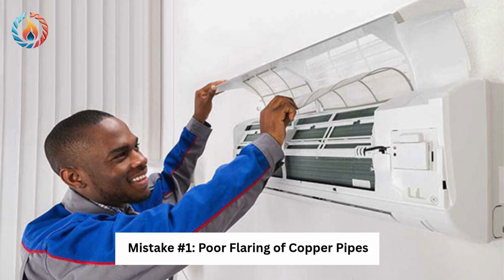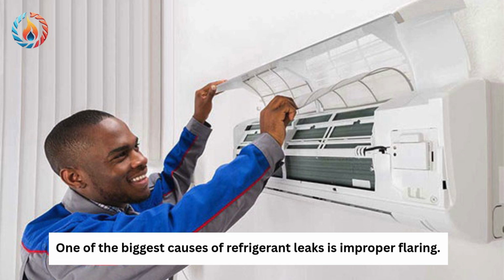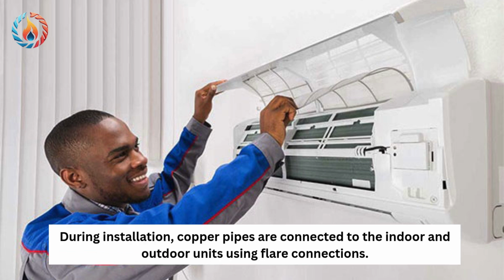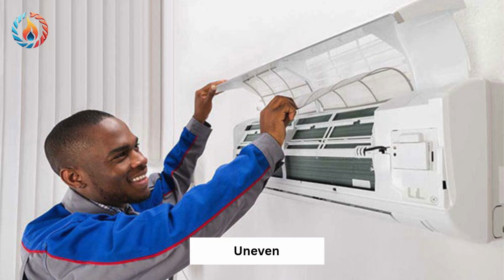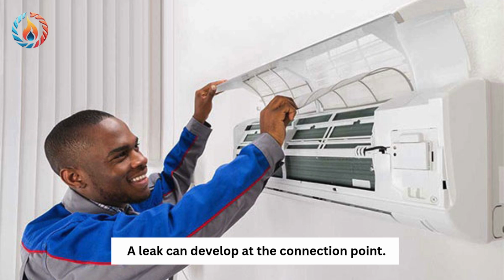Mistake number 1. Poor flaring of copper pipes. One of the biggest causes of refrigerant leaks is improper flaring. During installation, copper pipes are connected to the indoor and outdoor units using flare connections. If the flare is uneven, cracked, overflared, or underflared, a leak can develop at the connection point.